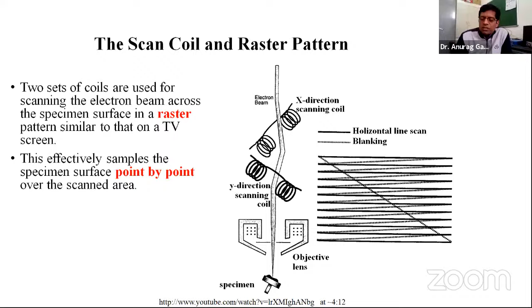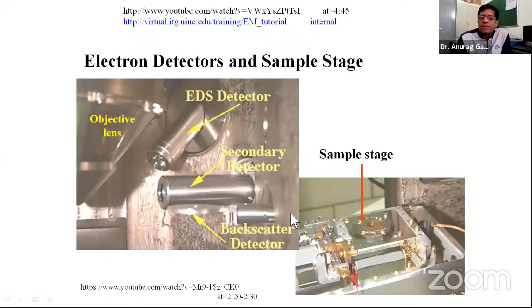These are the EDX detectors. The EDX detector is basically for elemental analysis, so you can analyze the elemental composition. This is energy dispersive X-ray analysis. But for image production, there will be the backscatter detector or the secondary electron detector. These 2 detectors collect the scattered electrons in a particular range of energy. As I told you, secondary electrons have up to 50 electron volt energy, so they will enter the secondary electron detector, and those with greater energy are backscattered. They are then used to generate the image of our sample. That is how the image will be formed.